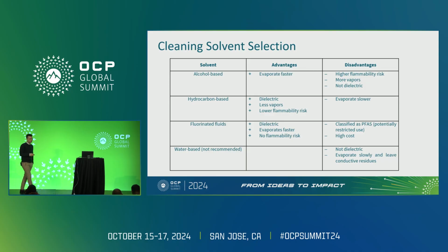I think the consensus around water-based was fairly clear. Some people are using water-based degreasers, but the general consensus was that it was not a good idea because they're not dielectric. So any small remains of the degreaser will subsequently contaminate the fluid afterwards. They also evaporate fairly slowly and are conductive, right?